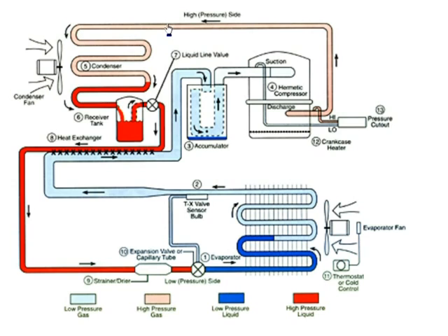On a 10 SEER, I believe it's 20 degrees. If it's like a 17 SEER, you're only adding like 14, 15 degrees. Some of the 8 SEER units, you could add 25 degrees. So the lower the efficiency, the more temperature you have to add. The higher the efficiency, the less temperature you have to add.